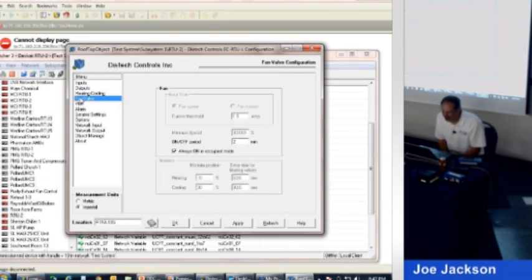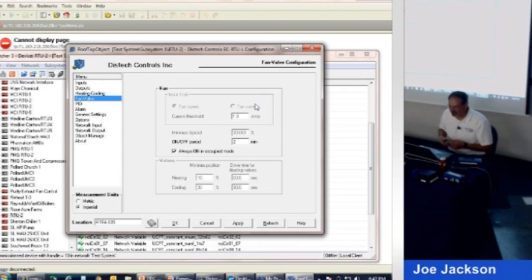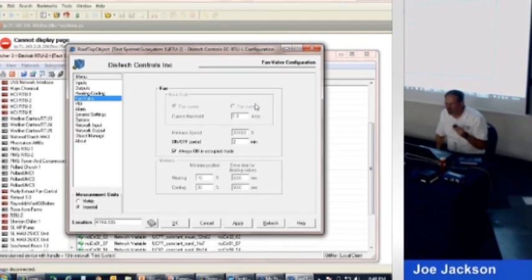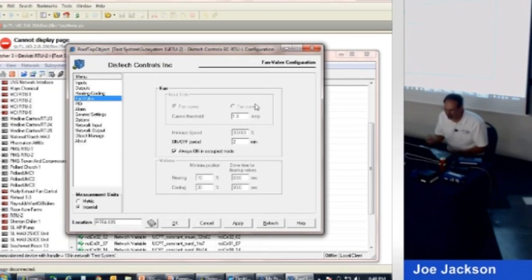We got some fan and valves here. If we selected a different type, this guy here can actually read current in amps. So if we just set it up for, we want to declare the fan on when this thing hits 1 amp. So you could actually pull the belt off, measure the current, say, oh, we've only got a half amp without the belt on, and we got a full amp with the belt on. You could actually use this guy to tell if the belt had been thrown or not. The current sensor we selected in the setup was just an on-off. It's either there or it's not. So this wouldn't actually apply.